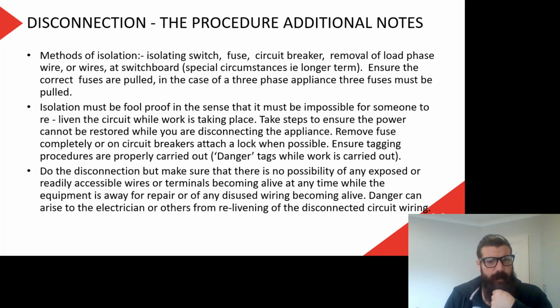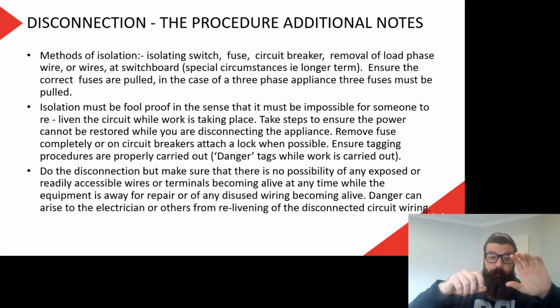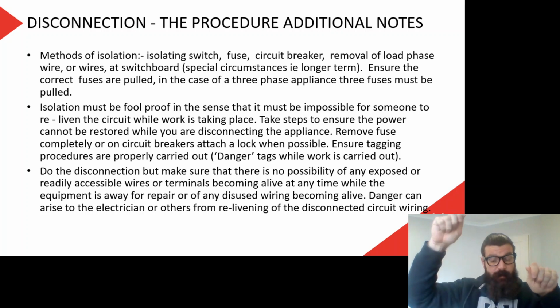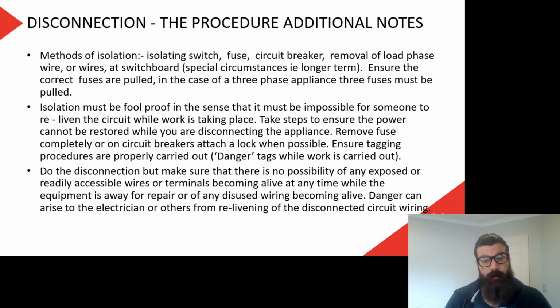There are a number of methods of isolation here. So we've got an isolating switch, which we talked about, a fuse or a circuit breaker, which are both in the switchboard. But also removal of load phase wire or wires at the switchboard. So that's where, as I said before, you get the circuit breaker and you physically disconnect the wire out of the top of it so it cannot be turned back on. It says there's special circumstances, i.e. longer term. Yeah, you might do something like that where you are permanently removing something, let's say you're taking out a hardwired compressor. We don't need to leave that circuit live, so we'd probably go back to the switchboard and physically disconnect that cable out of the switchboard.